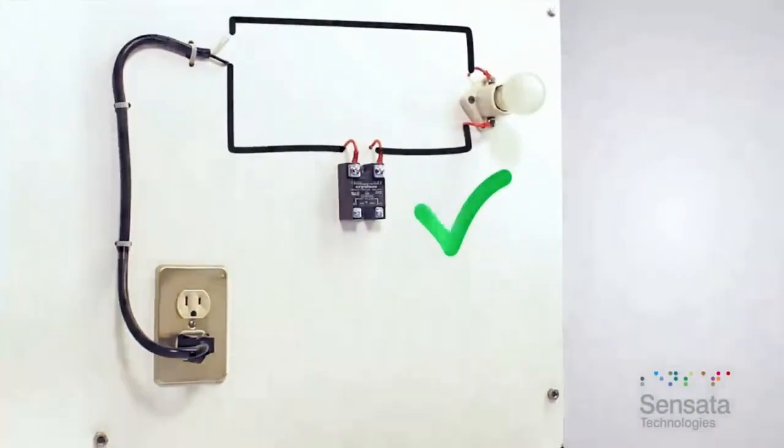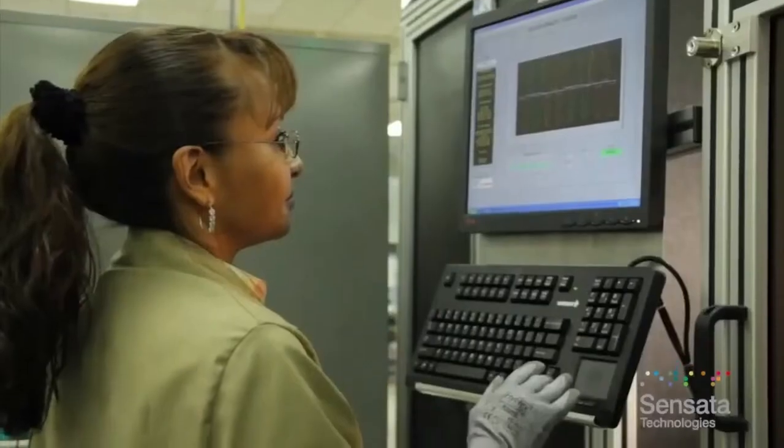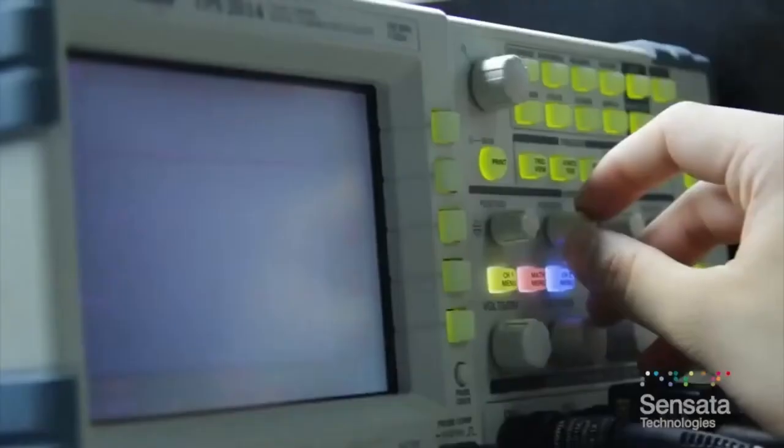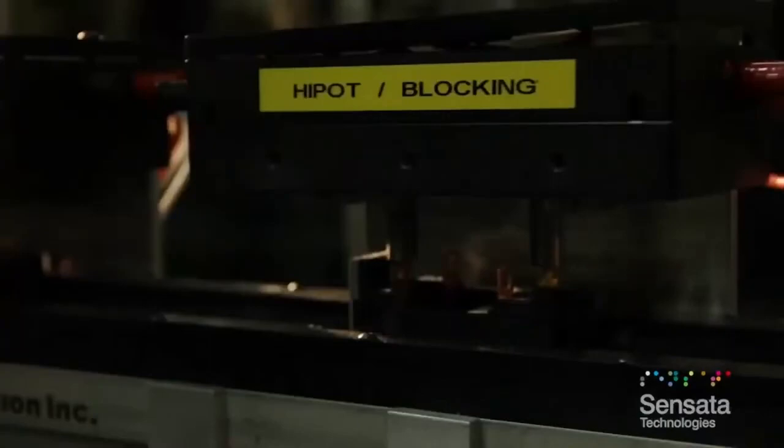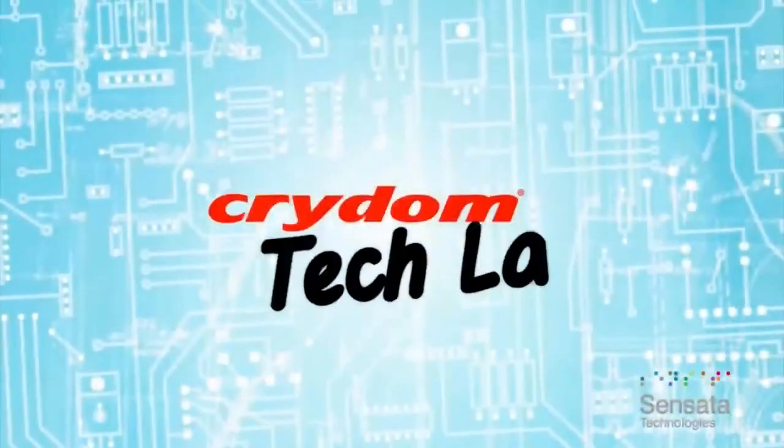Removing and applying the battery should correspondingly flash the lamp on and off. As seen here, this solid state relay passes the basic operational test. There are many more detailed tests that are performed on SSRs at the factory during production, but a simple bench test performed as shown provides a quick indication of SSR operation. We hope this has been helpful. Thanks for watching this edition of Crydom Tech Lab.